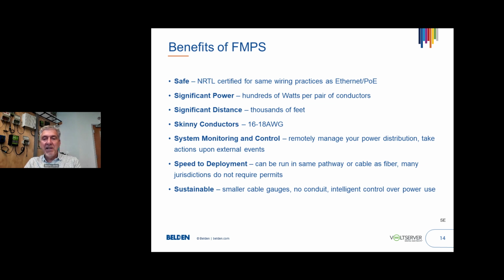So you're looking at a digital technology that actually embeds data within the FMP protocol. So in the VoltServer implementation of FMP, we're sending pulses of power that also have data interleaved with that power. And that's sent as a discrete pulse from one place to another, and it's checked every time those little packets go out. So when we make those packets very, very small in energy content, and we're tracking every one, we can tell if that packet is going into a human body or a source of fire versus going to the right place, which is a remote load.